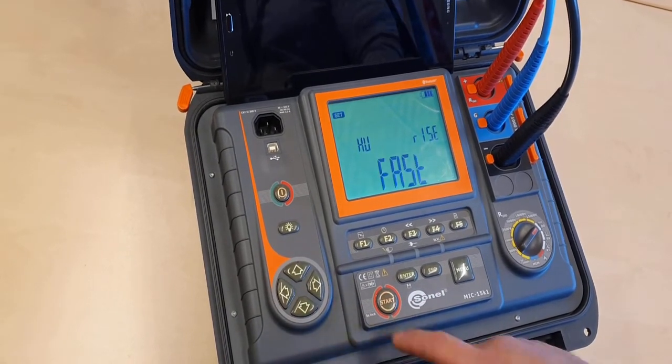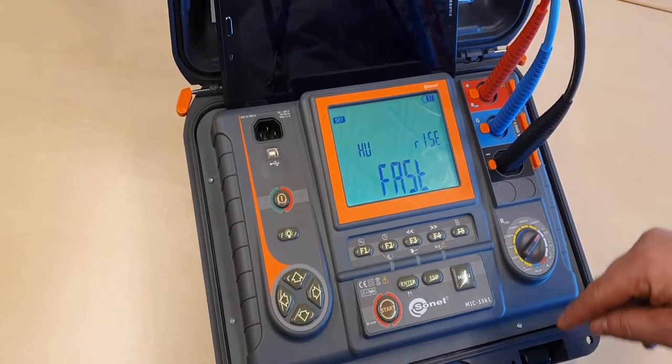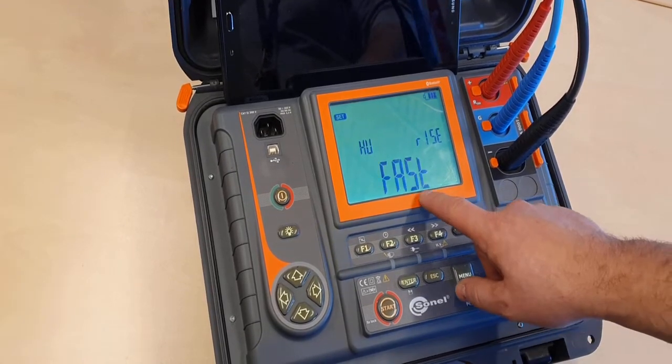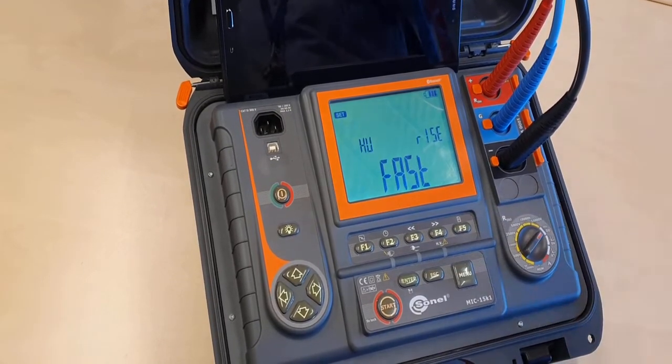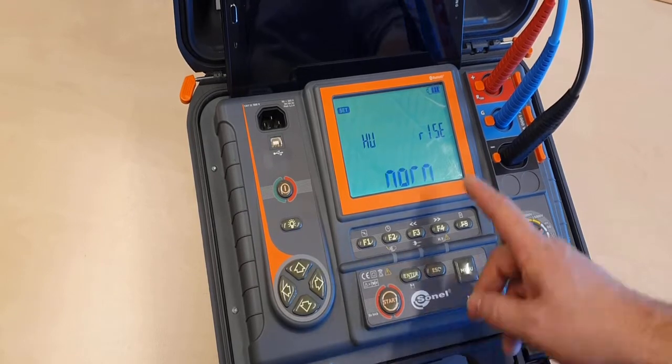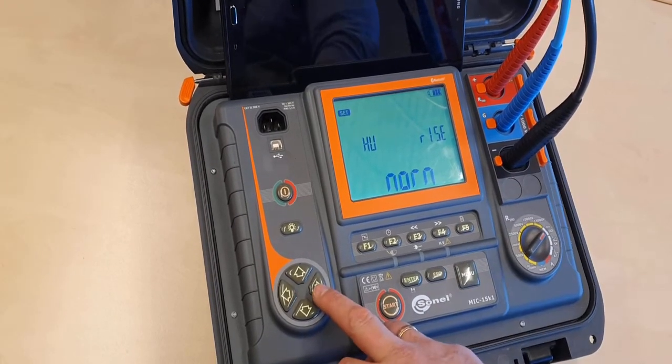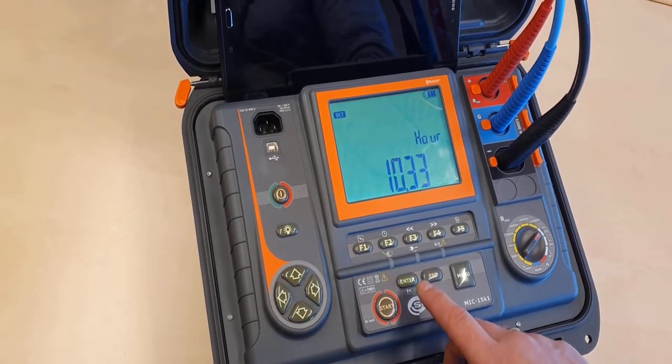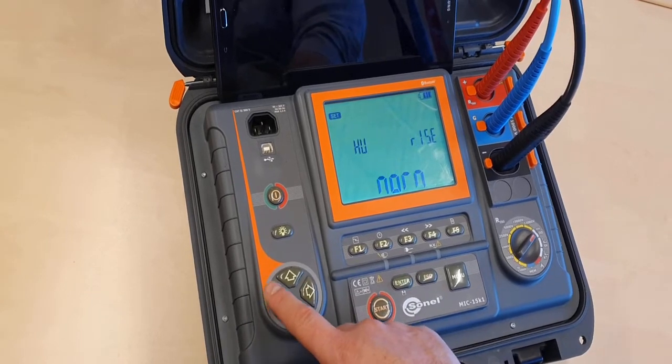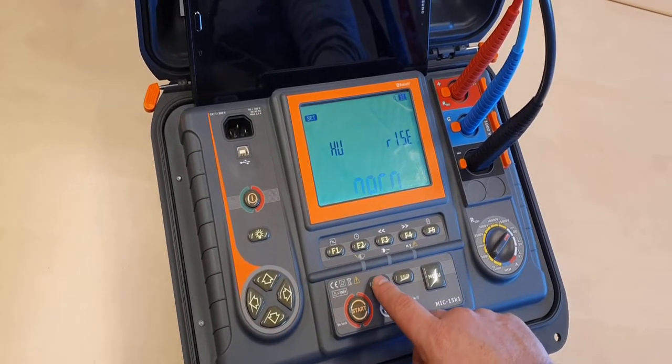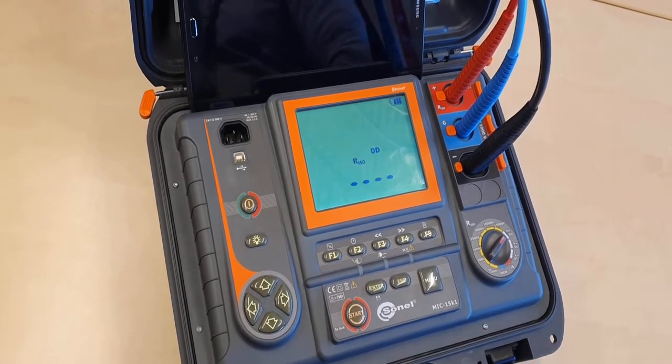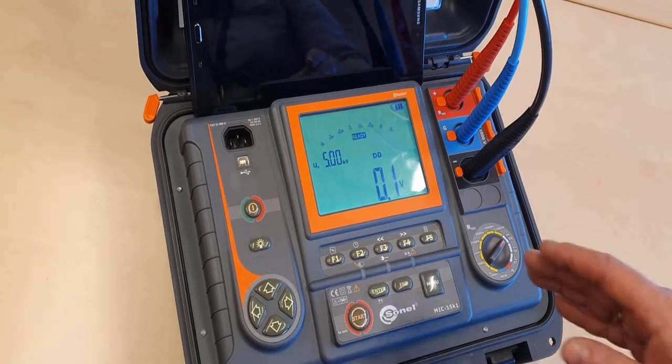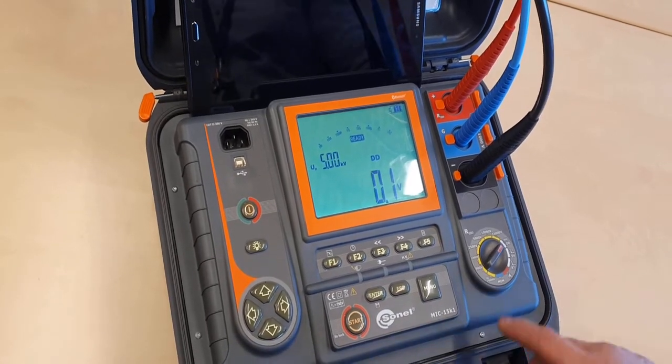The next setting is HV, which is the speed of the voltage rising. With the fast setting, we will quickly reach the value of the testing voltage, but I use normal. I am pressing ENTER to confirm the setting and the meter goes to the standby mode before measurement.